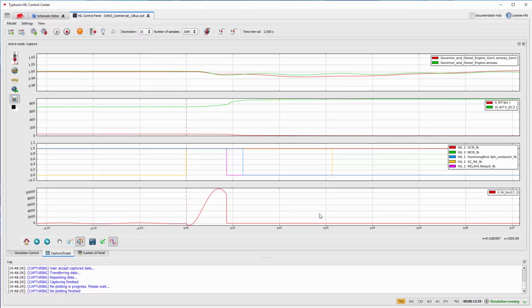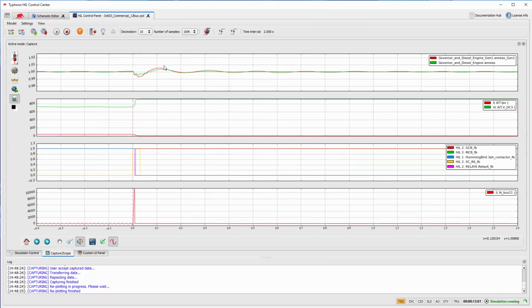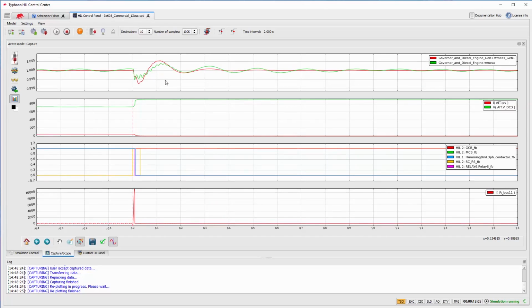The Hummingbird inverter disconnected in about 12 milliseconds. That is slower than the Relay 6 reaction, but even though the short circuit was cleared, the inverter suffered a DC link over voltage and had to disconnect. The AIT inverter used in this model does not have a contactor control, thus it does not disconnect from the grid, but stops its operation. We can see that it stopped its operation in 50 milliseconds, also due to DC link over voltage.